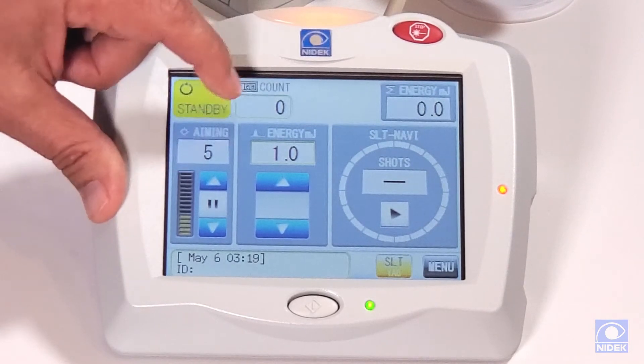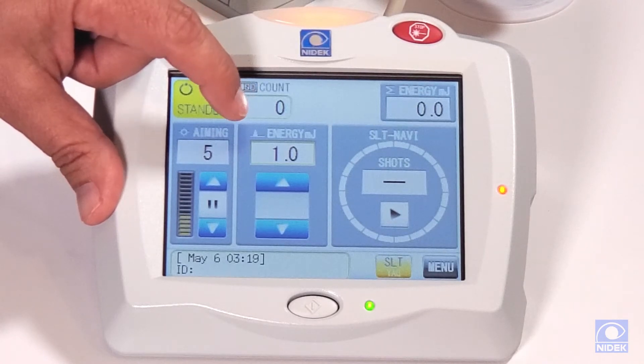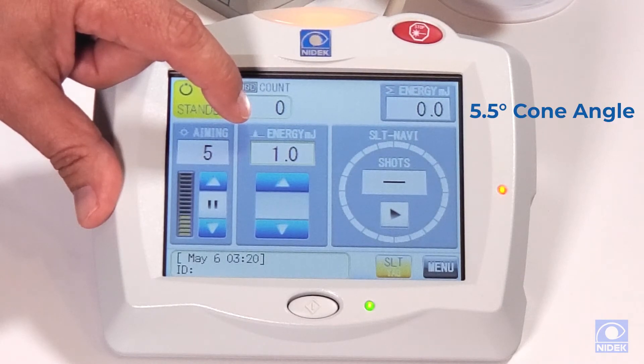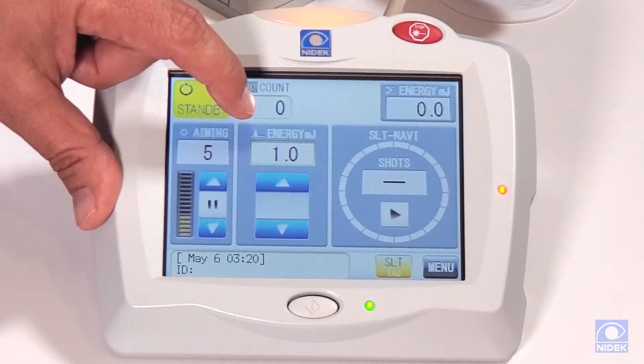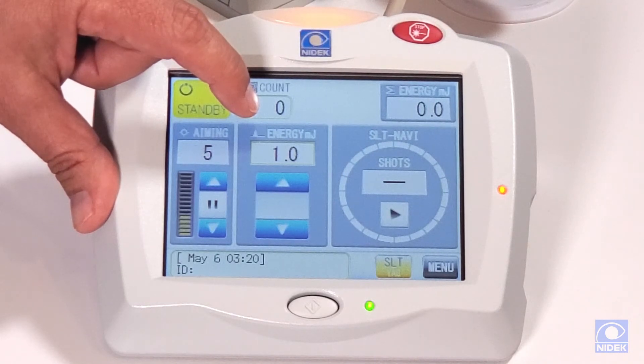One important feature of the SLT mode is that we have a treatment cone on the cornea of a 5.5 degree cone angle, as opposed to a 3.0 degree cone angle. This is designed to reduce the energy density on the cornea for tissue sparing, because you may want to come back and retreat this patient.